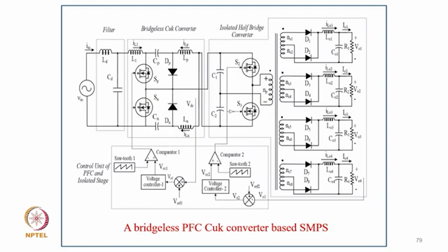And this is the case with the bridgeless converter. You can clearly see here there is no diode bridge rectifier, and you will get a regulated DC output voltage. The input EMI filter size is also reduced because the input inductor, L1, is designed for CCM. Only the output inductors LP and LN are designed for DCM. You sense the input voltage and input current, and you get a well regulated 300 volt DC link, considered as a retrofit solution to replace the diode rectifier at the input, and you get inherent power factor on the supply side also.